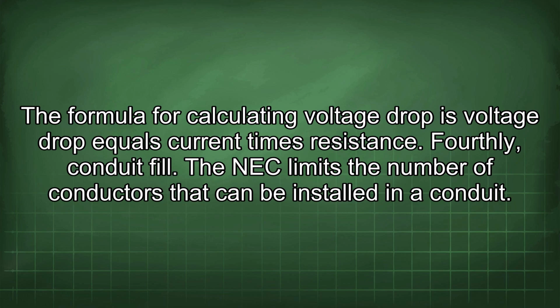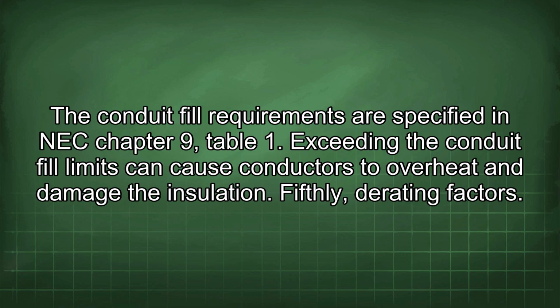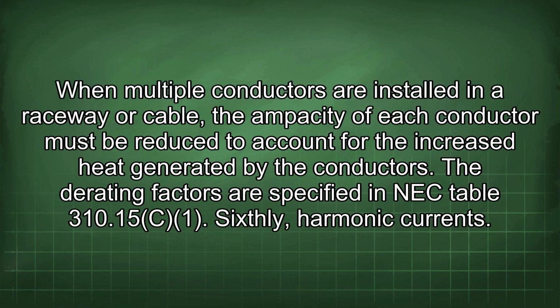Fourthly, conduit fill. The NEC limits the number of conductors that can be installed in a conduit. The conduit fill requirements are specified in NEC Chapter 9, Table 1. Exceeding the conduit fill limits can cause conductors to overheat and damage the insulation. Fifthly, derating factors. When multiple conductors are installed in a raceway or cable, the ampacity of each conductor must be reduced to account for the increased heat generated by the conductors. The derating factors are specified in NEC Table 310.15(C).